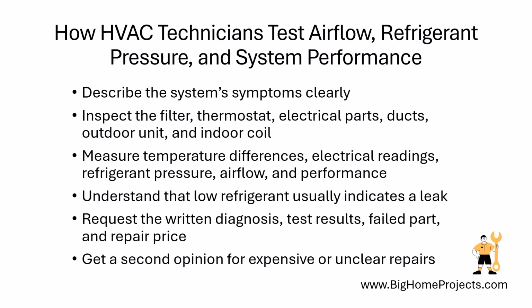A useful detail is that low refrigerant usually means the system has a leak, because refrigerant is not normally used up like fuel. Simply adding more refrigerant may cool the house temporarily while allowing the leak to continue.